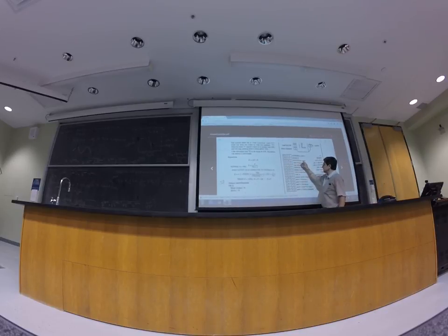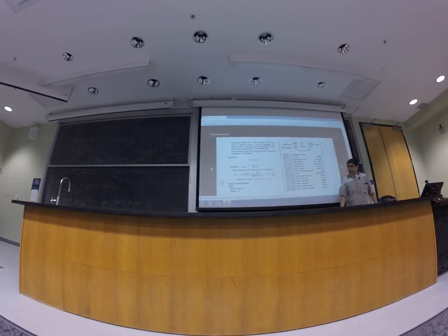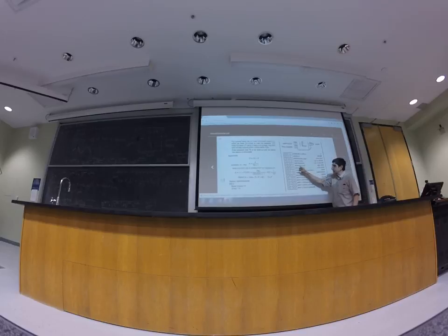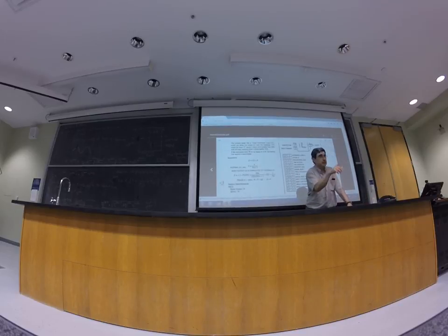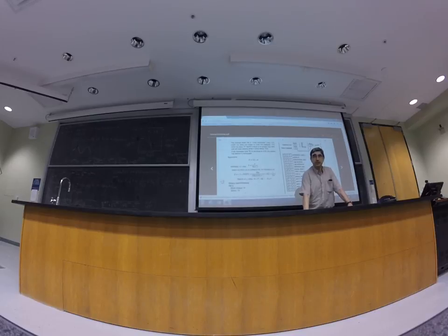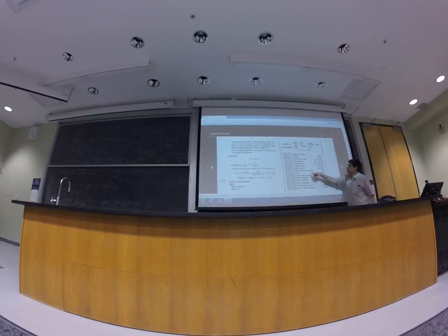And software are the S's, and SPG, proportional gain, that's our KC. Time integral, that's our tau I. Time derivative, that's our tau D. Derivative gain, as we will see, this is related to that alpha. That has to do with our filter. So filtering is embedded into that derivative gain. Very important, the first two ones.